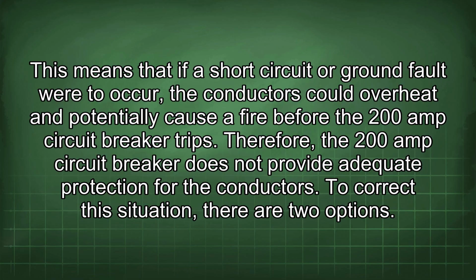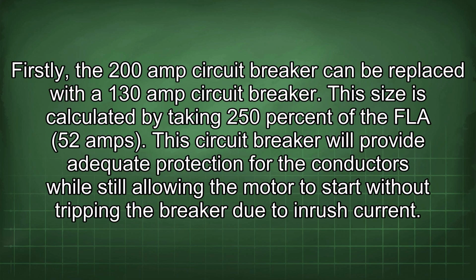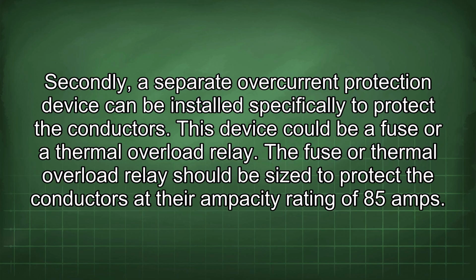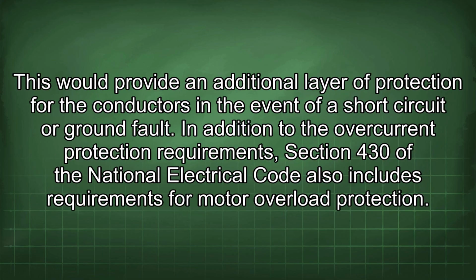To correct this situation, there are two options. Firstly, the 200 amp circuit breaker can be replaced with a 130 amp circuit breaker. This size is calculated by taking 250% of the FLA of 52 amps. This circuit breaker will provide adequate protection for the conductors while still allowing the motor to start without tripping the breaker due to inrush current. Secondly, a separate overcurrent protection device can be installed specifically to protect the conductors. This device could be a fuse or a thermal overload relay. The fuse or thermal overload relay should be sized to protect the conductors at their ampacity rating of 85 amps. This would provide an additional layer of protection for the conductors in the event of a short circuit or ground fault.